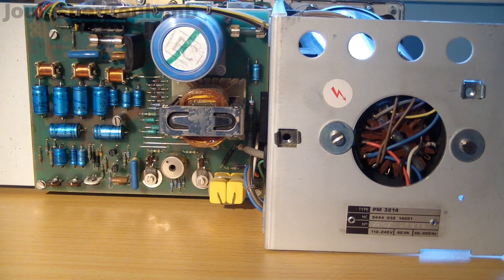Another slightly unusual and useful feature of this oscilloscope is that its chassis is not connected to mains safety earth. It's double insulated due to the mains transformer being housed in an isolated plastic box on the rear panel. This can be very useful, as it means it can be connected to a device under test without having to tie some part of that device's internal circuitry to the mains earth.